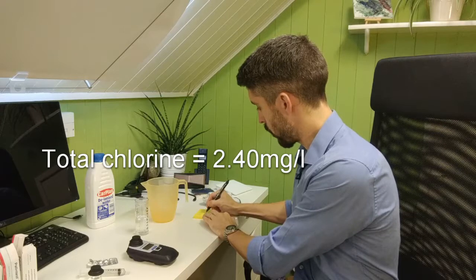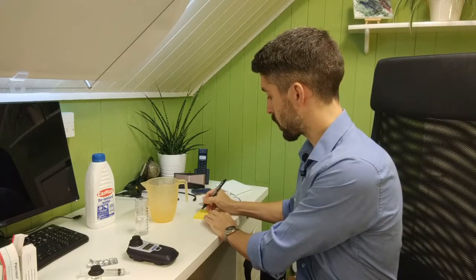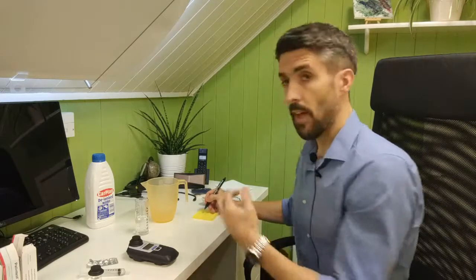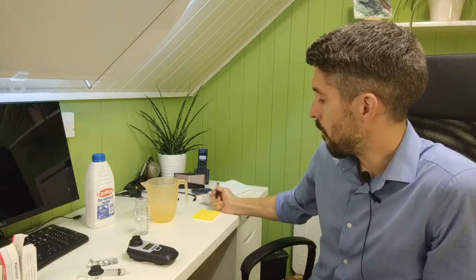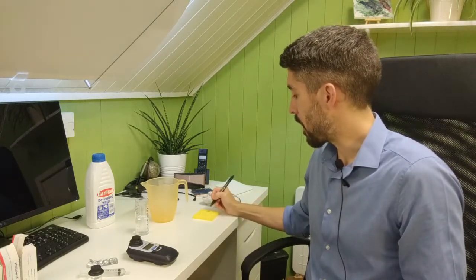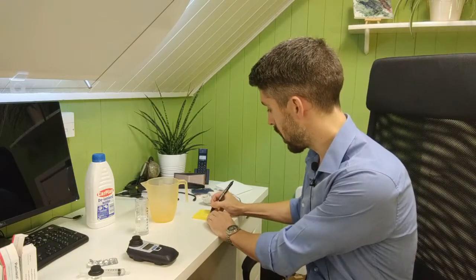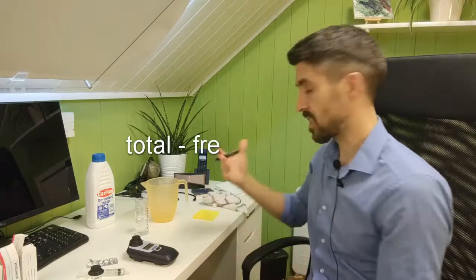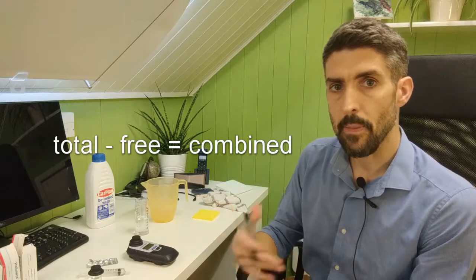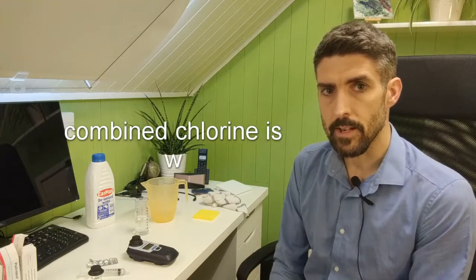So 2.40 was the total. 2.28 was the free. So of that 2.40 total chlorine, we know that 2.28 milligrams per liter is in the form of free chlorine. So that tells us that we've got a combined chlorine level of 0.12, because basically that's the difference between the total chlorine and the free chlorine. So you basically take the free chlorine amount value away from the total chlorine, which leaves you with the amount of combined chlorine. There's no actual tablet test for combined chlorine. What you do is you test for free, then you test for total, and then you take the free value away from the total value, and that tells you what level you've got in terms of combined chlorine.